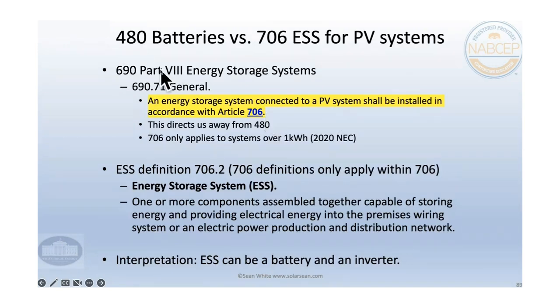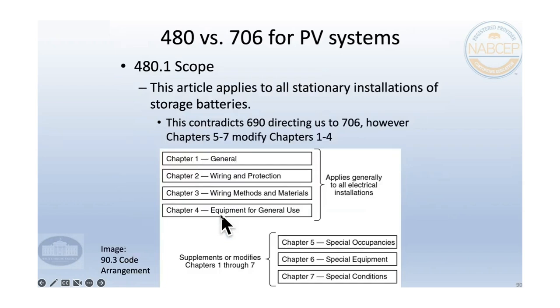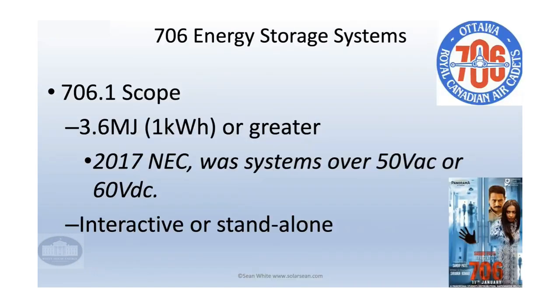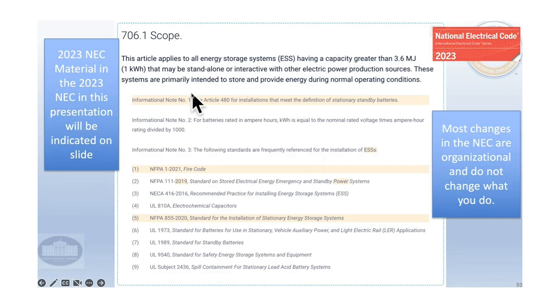So 690 supersedes Articles 1 through 4 and modifies and supplements, and so does 706. All these different things direct us away from 480, so we don't need to really worry too much about 480. So let's get into 706. The scope of 706, they say, is for 1 kilowatt hour or greater. In the 2017 NEC, they were talking more about 50 volts or 60 volts. And it's funny because I'm in Tennessee, and I'm doing an NEC presentation tomorrow on the 2017 NEC. And here's the 2023 NEC.